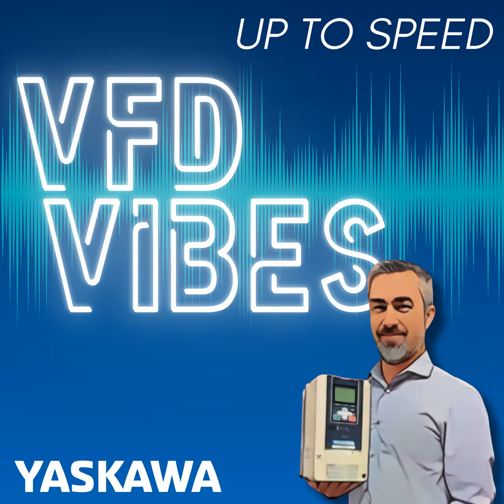By the way, the largest single-phase motor in the catalogs is about 10 horsepower. Beyond 10 horsepower, the starting requirements become more or less impractical.